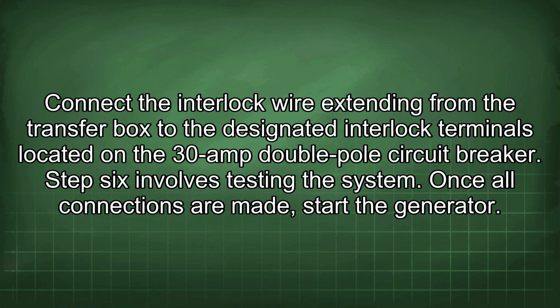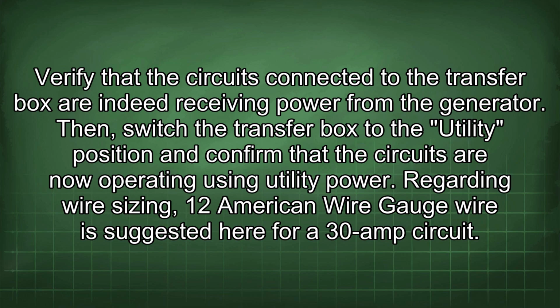Step 6 involves testing the system. Once all connections are made, start the generator. Verify that the circuits connected to the transfer box are indeed receiving power from the generator. Then, switch the transfer box to the utility position and confirm that the circuits are now operating using utility power.